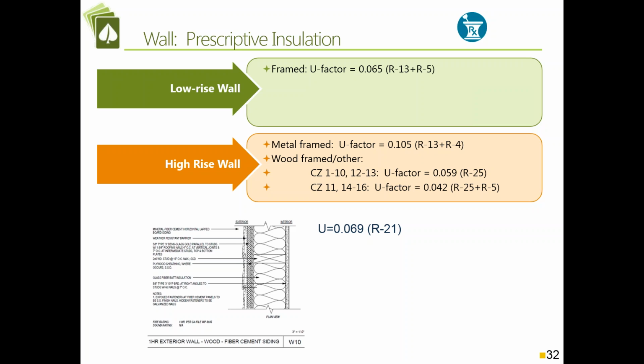The only way we're going to meet that is with at least an R5 exterior insulation. The low-rise mandatory U factor is 0.102, and the high-rise mandatory U factor is 0.105. So the mandatory wall requirement in low-rise is actually more stringent than high-rise. Metal framing in low-rise will be the same R13 plus, but with at least an additional R5 exterior insulation.